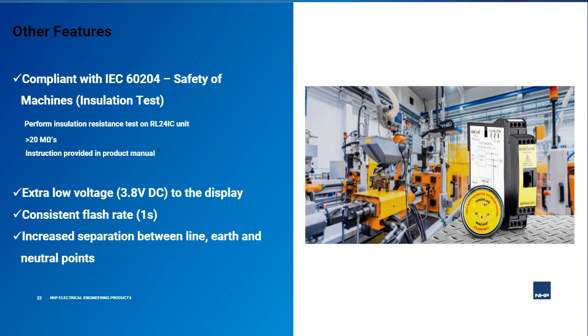There are other features of the REMLIVE unit that should be highlighted. For example, the upgraded REMLIVE unit is compliant to the IEC 60204 standard on safety of machines with respect to insulation tests on electrical devices. Insulation resistance tests can be performed on the device if required. From the testing that was done before product release, the insulation resistance for the unit measured at greater than 20 megaohms. The instruction on conducting the insulation resistance test on the device is described in the manual supplied with the product.